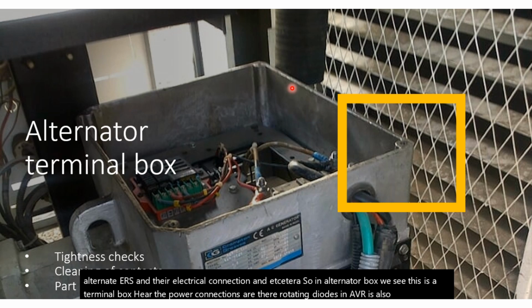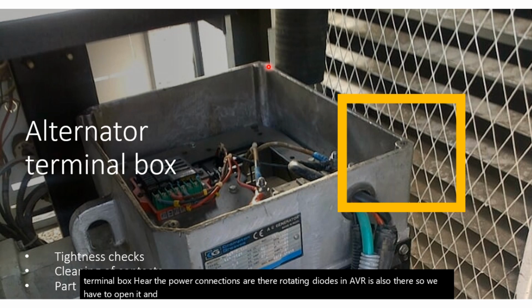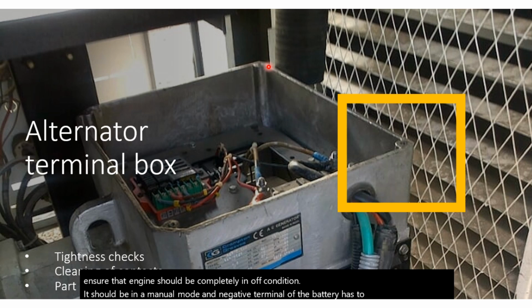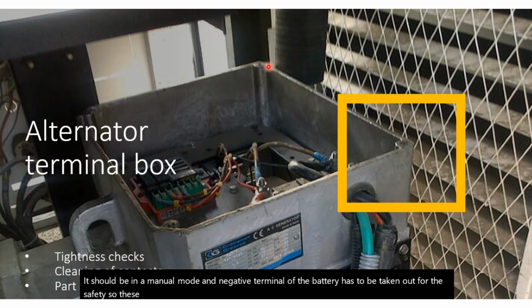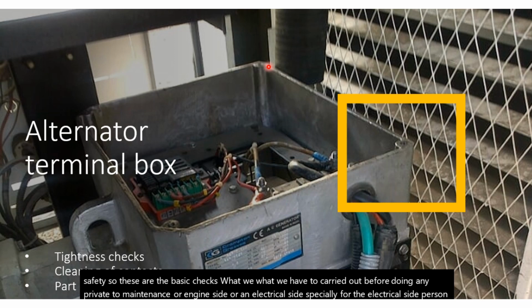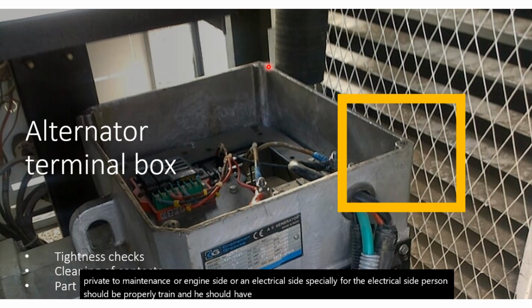So we have to open it, and again, as we discussed, before doing any preventive maintenance, we have to ensure that the engine is completely in off condition. It should be in manual mode, and the negative terminal of the battery has to be taken out for safety. So these are the basic checks we have to carry out before doing any preventive maintenance on the engine side or the electrical side. Especially for the electrical side, the person should be properly trained, and he should have a proper license as per the authority wherever this DG is installed to carry out the maintenance.